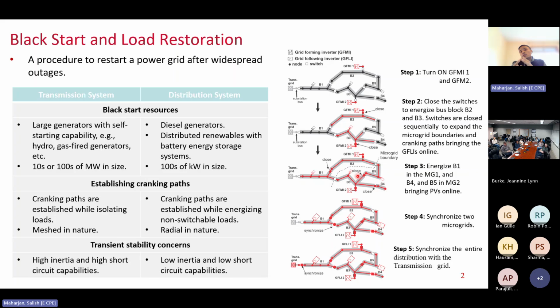And at some point when we have energized all the bus blocks, we want to synchronize those two microgrids. The synchronizing helps to augment the power and energy capacity of individual microgrids. This augmentation may sometimes be significant to restore some large amount of loads. And finally, when the transmission grid comes online, we want to synchronize the entire distribution system with the transmission grid so that the whole distribution system can run continuously for a long period of time.